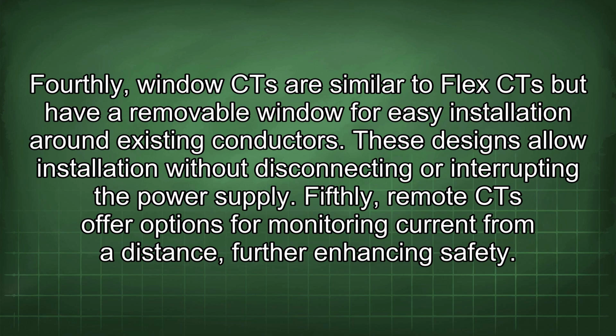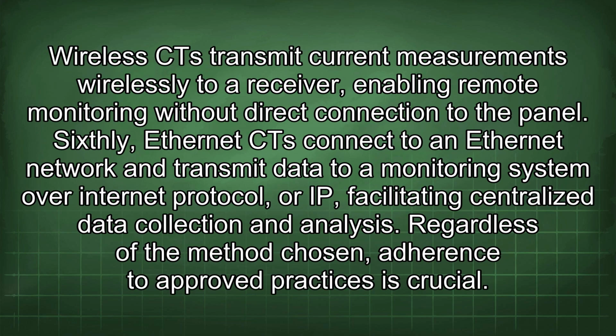Fifthly, remote CT offer options for monitoring current from a distance, further enhancing safety. Wireless CT transmit current measurements wirelessly to a receiver, enabling remote monitoring without direct connection to the panel. Sixthly, Ethernet CT connect to an Ethernet network and transmit data to a monitoring system over Internet Protocol, or IP, facilitating centralized data collection and analysis.